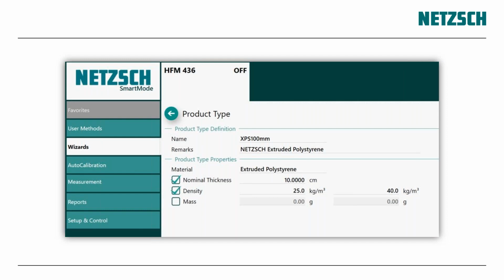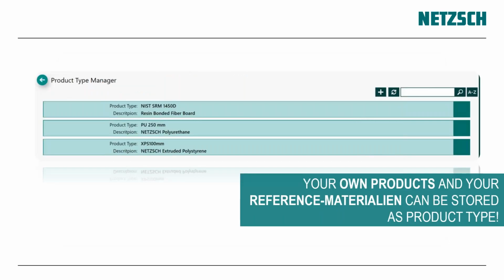If you insert the sample and the instrument tells you, by entering the weight of the sample, that the density is not in that range, the instrument gives you the first alert that you don't have to start the thermal conductivity measurement because it's already out of the density range. This is a real first indicator that there is somewhere a kind of quality issue. You can add several product types, also reference materials. So you can also do a statistic on reference material based on that product type.